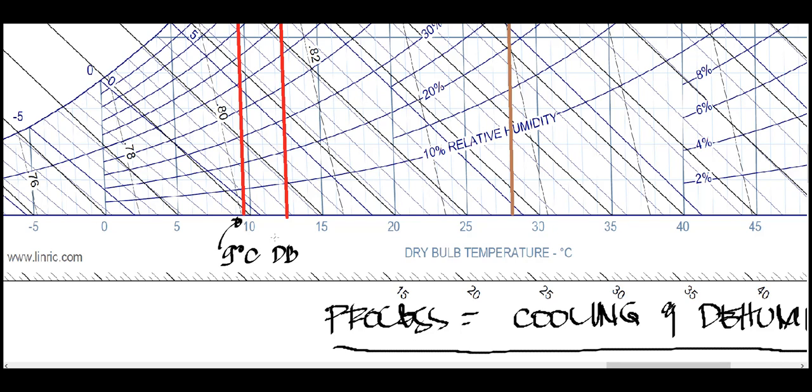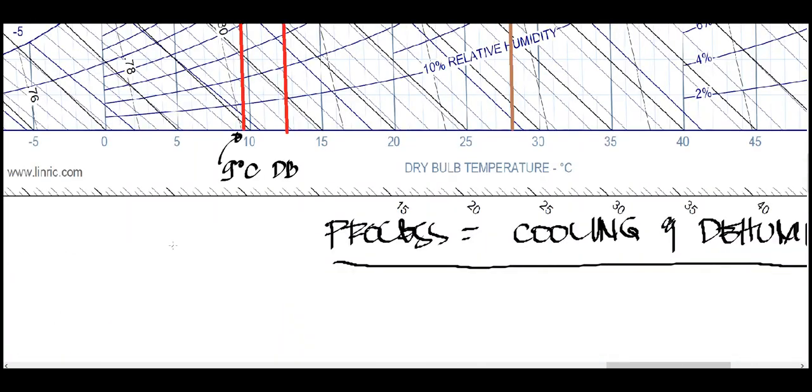So this is also the temperature at which, if you're going to expose the apparatus or the surrounding duct of the system below 9 degrees Celsius, for example, if we have your FCU here, the dew point temperature is 9 degrees.